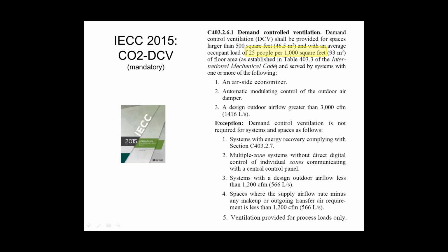Theoretically, if you had a very simple system, let's say you had a school gymnasium and you had like 5 feet of duct and you just wanted to put it in the return duct there, I would personally be okay with that. But as soon as you have a zoning system with VAV dampers or something like that, you definitely cannot put it in the return duct, right? Because if I put it in the return duct, I'm sensing the average CO2 of all of these zones. And how can I start throttling back the airflow for specific zones if I don't know what's going on in those specific zones? So on a VAV system, you've got to put one on every single damper.